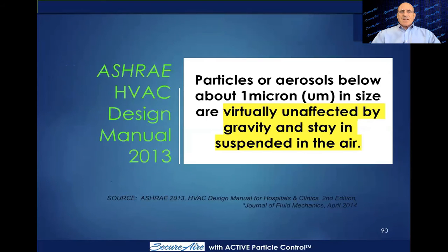So let's go ahead and consider this. ASHRAE says that particles below 1 micron in size are virtually unaffected by gravity and stay suspended in the air. That means most of what's in the air by count at 1 micron and smaller is going to be suspended in the air. Even normal air movement will not shake it loose. I use the analogy of suspended in the air like fruit in gelatin.